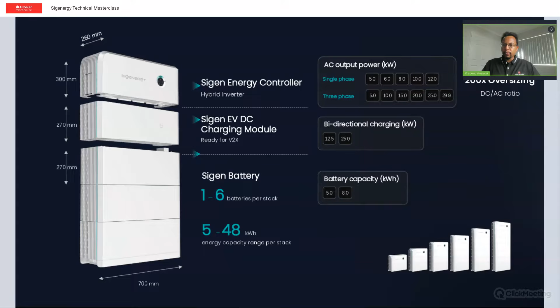For bidirectional charging, there are two sizes, 12.5 kilowatts or 25 kilowatts - that's pure DC charging. There's also an optional AC charger, which we'll go into later. Battery capacity, as already touched on, is 5 kilowatt hour or 8 kilowatt hour modules. For oversizing, you can go over 200%, provided you don't exceed the datasheet parameters of short circuit current and open circuit voltage.